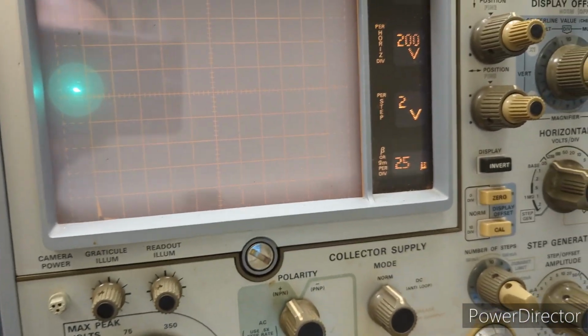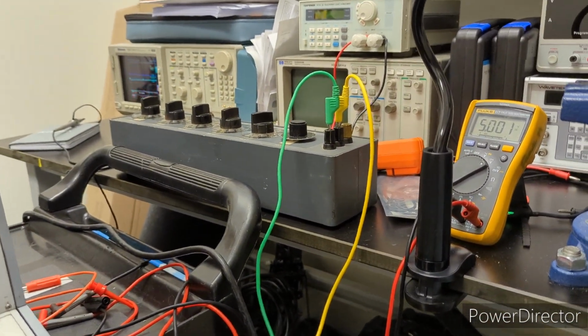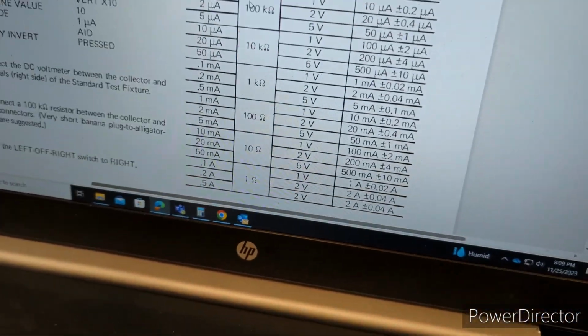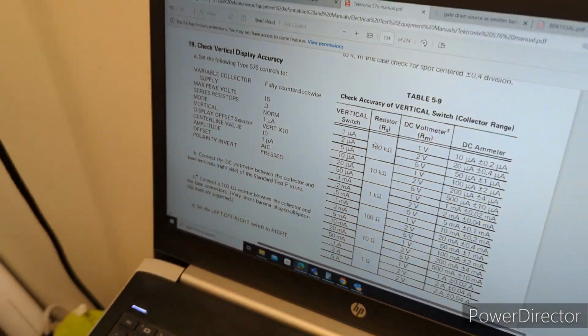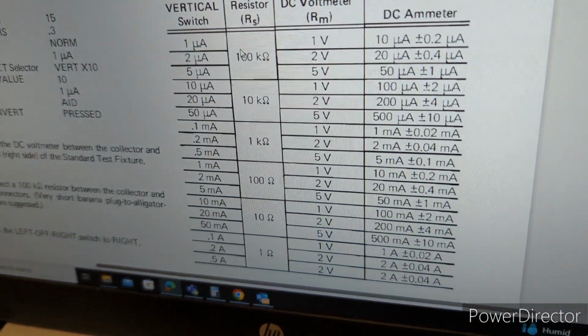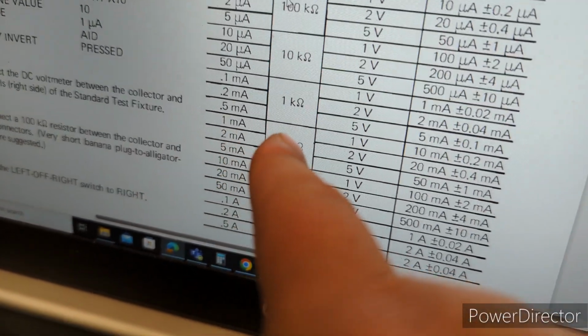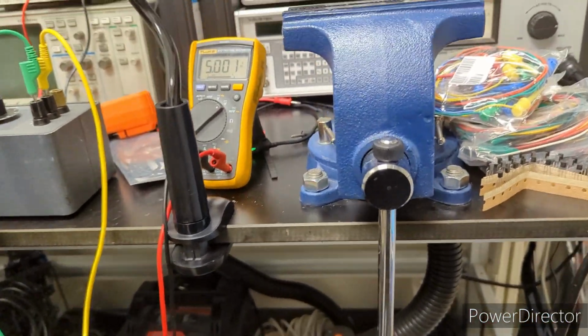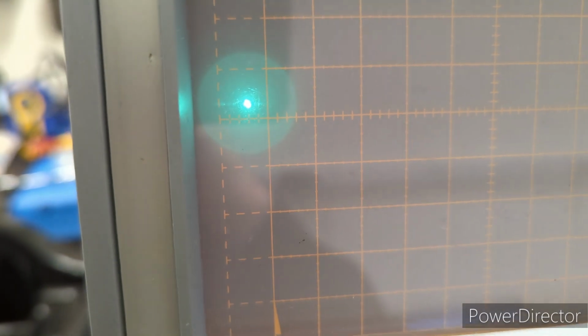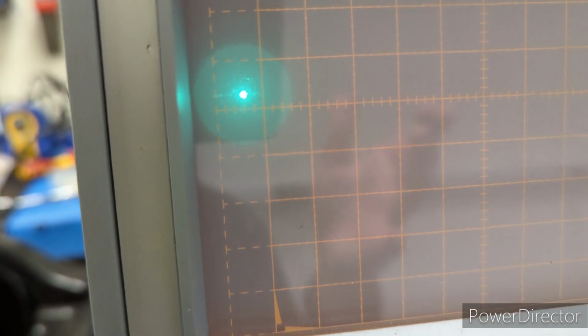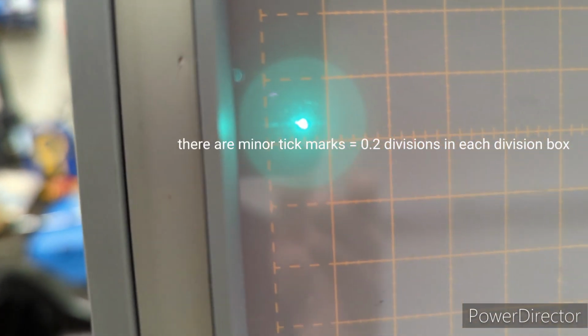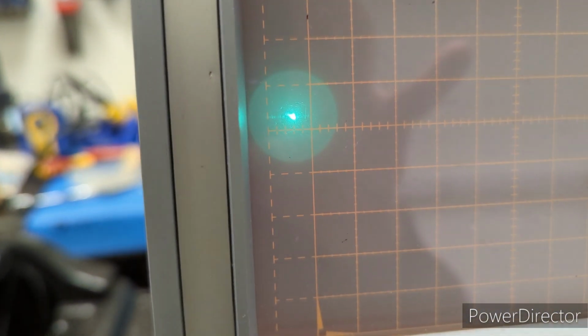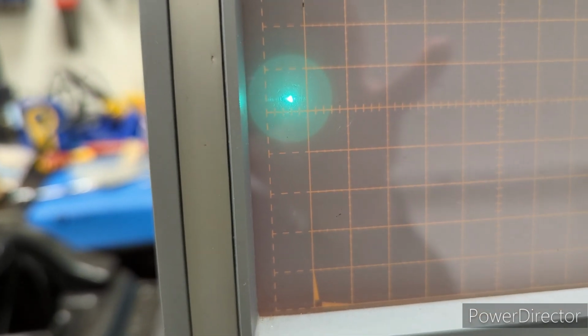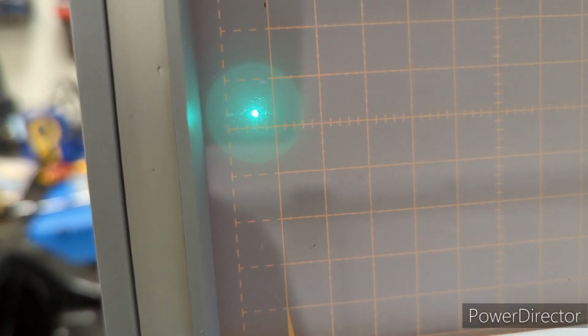Okay, so moving on through the vertical switch accuracy testing, we move down to a lower resistor, 1 kilo ohm. For that, the voltage readings on the multimeter start to get a little bit more accurate. For example, I'm checking the 0.5 milliamp setting, so I should be getting 5 volts with the 1 kilo ohm resistor across the collector and base input. You can see on the display the trace is a little bit off the center graticule, but there is a spec. It's plus or minus 0.4 divisions. I don't know how they measure 0.4, but the trace is clearly within plus or minus 0.5 division, so it's still within the spec, which is good.